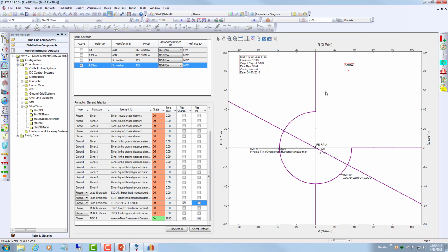We also need to look at the wind turbine capabilities, to make sure what kind of reactive power support is available, and when we go to zero power, whether the full reactive power is available or not. All those things can be incorporated as part of the ETAP projects to do the study in the StarZ mode, to make sure that the directional overcurrent protection element is reliable and there won't be any false trip in the system.